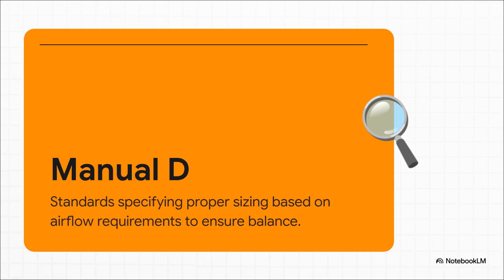And operating right alongside that is Manual D. While Manual J dictates the size of the core machinery, Manual D is the strict science governing your ductwork sizing. Oversize your ducts, and you get massive velocity drops where air just awkwardly dumps out of the nearest vent, leaving rooms further away totally unconditioned. Undersize them, and you create high-velocity whistling that strains the blower motor. Manual D guarantees perfectly balanced, whisper-quiet airflow across every single room.